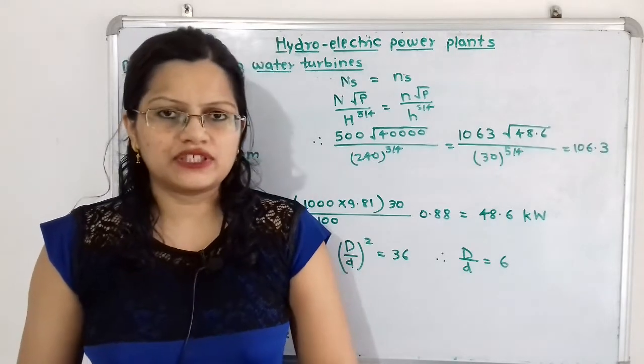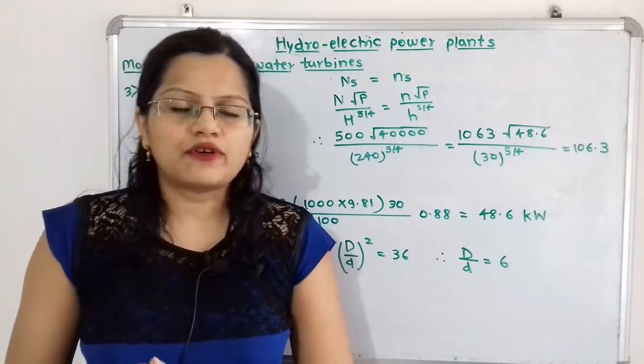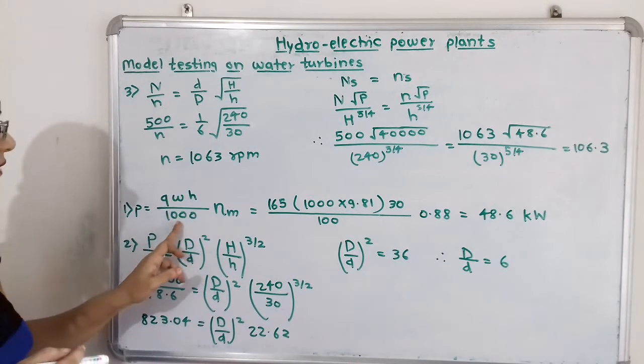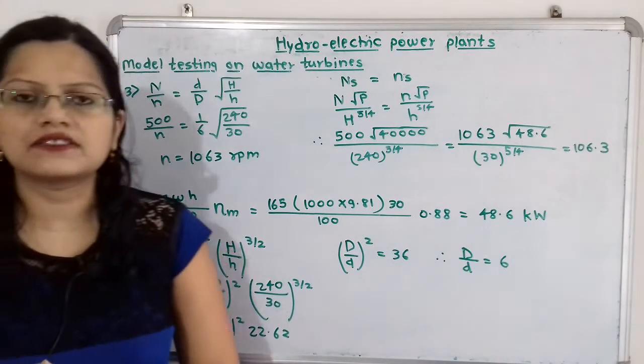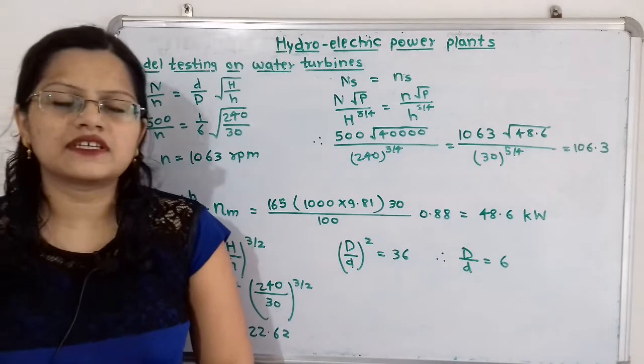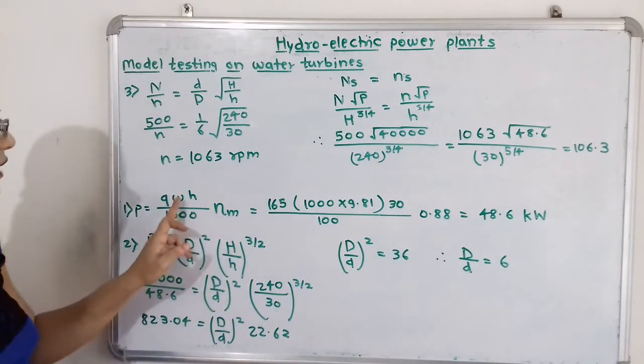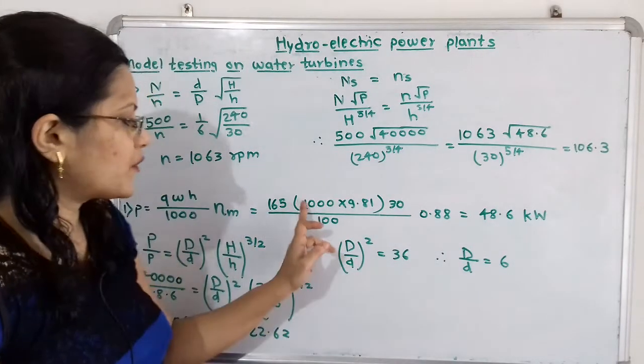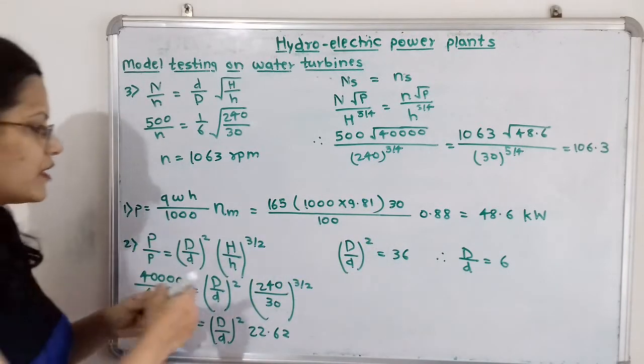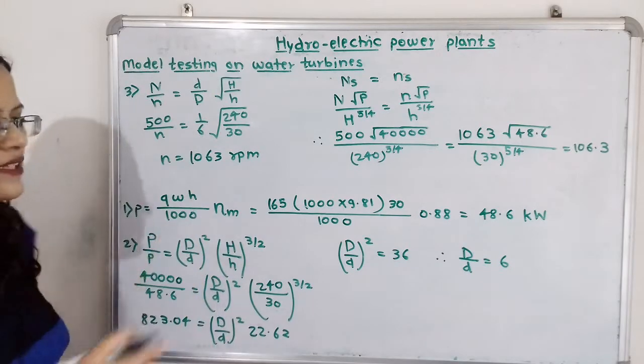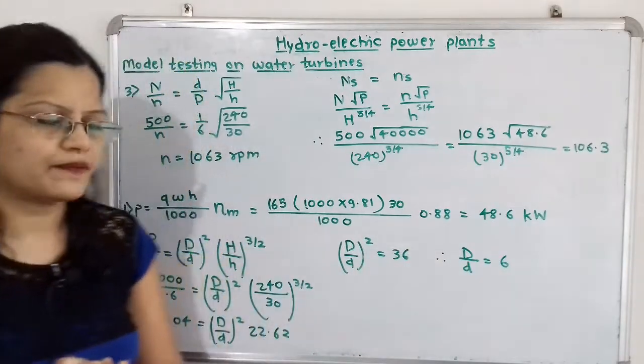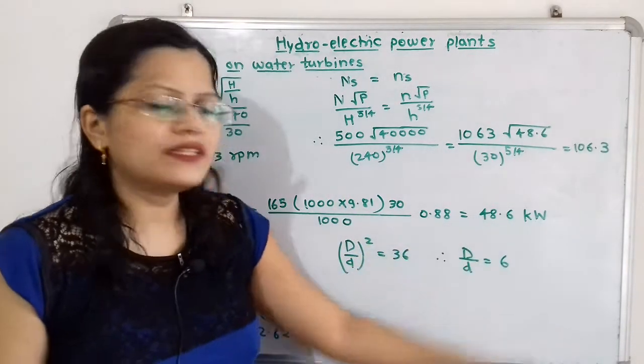Now we will move to calculations. First, we calculate the power developed by the model. Small p equals small q times W times h divided by 1000, multiplied by efficiency eta_m. Here q is 165 kilograms per second, W is density of water which is 1000 times 9.81, h is 30 meters, divided by 1000, multiplied by efficiency 0.88. When we calculate this, we get 48.6 kilowatt.